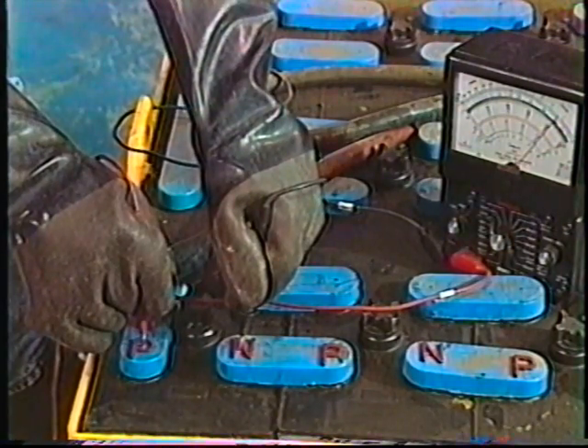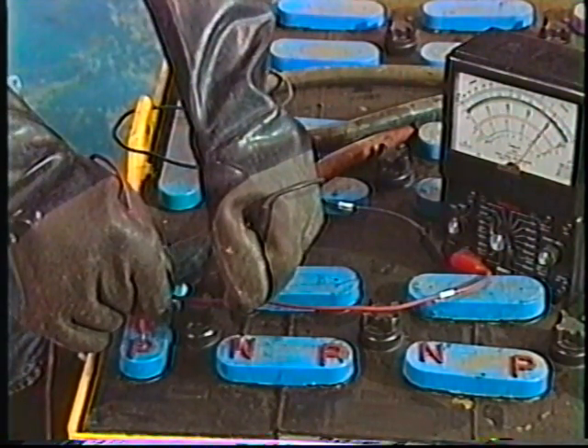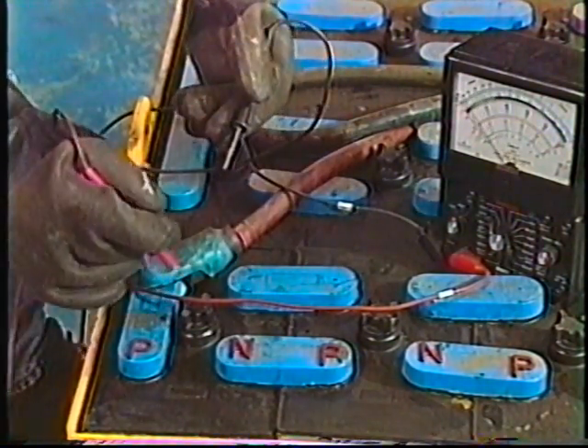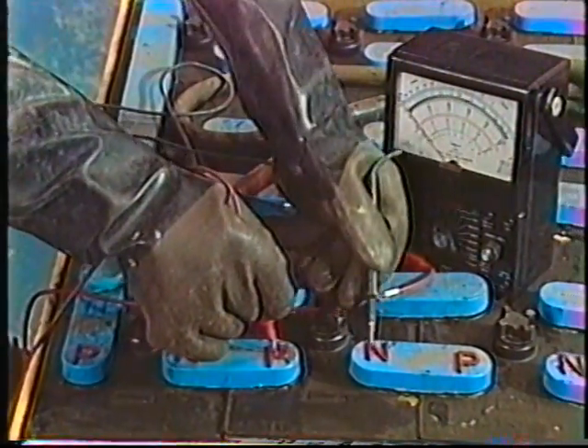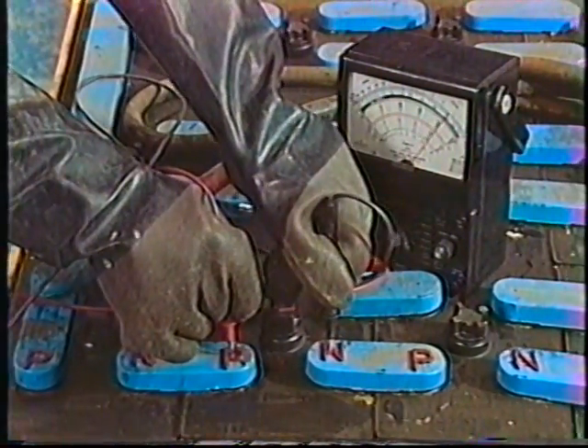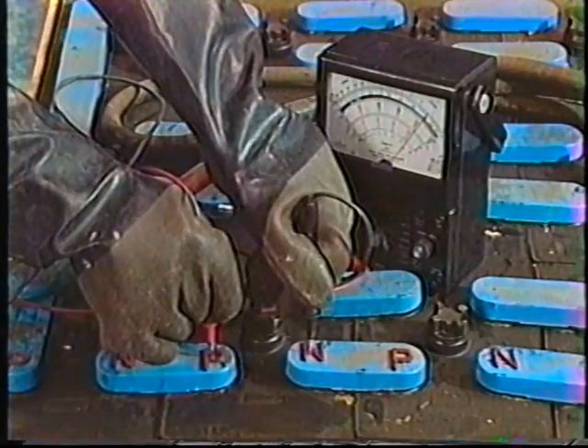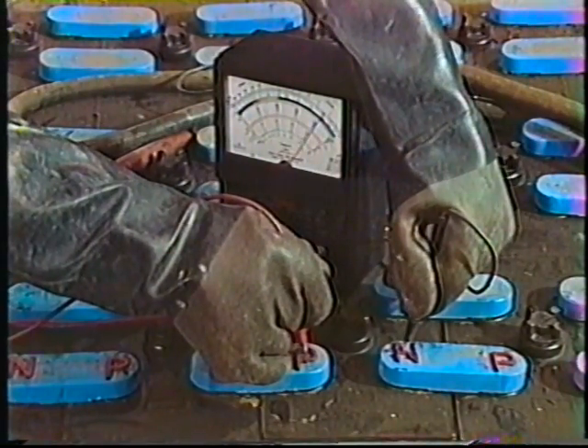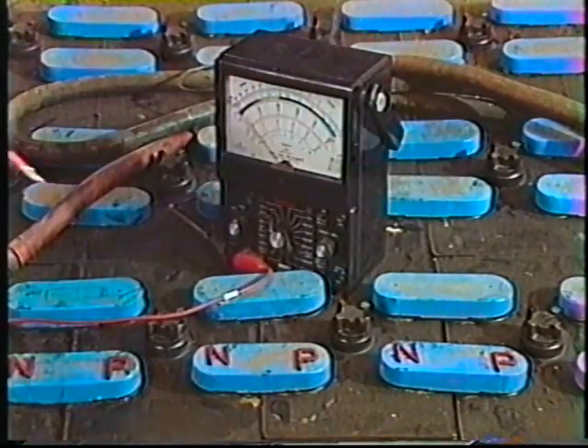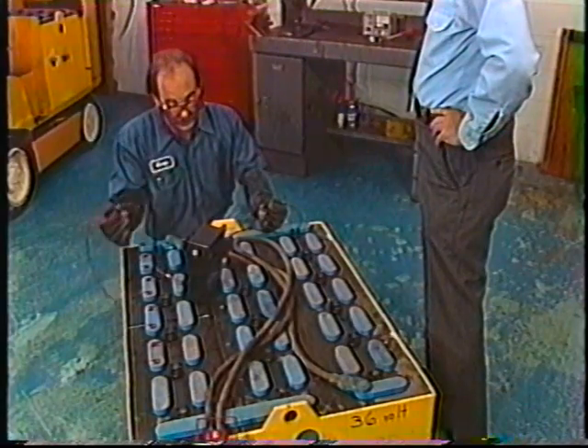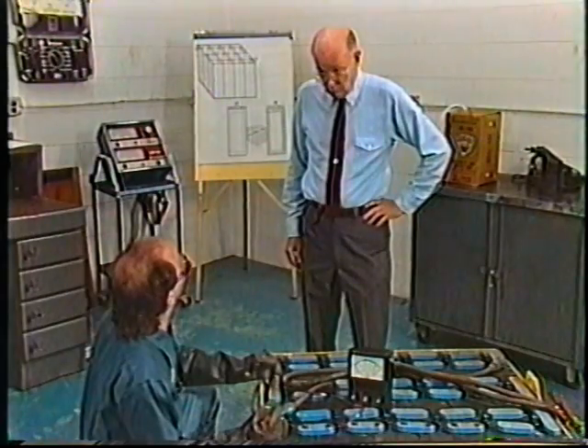We've added letters N and P here to help identify the terminals. The open circuit voltage should be about 2.1 volts per cell. Repeat this process for each of the cells and compare the readings. If there is a difference of 0.05 volts or more between any of the cells, there's a problem. Well, I got readings of 2.1 volts in all the cells except for this one, which reads 1.7 volts. So I guess there's a problem.